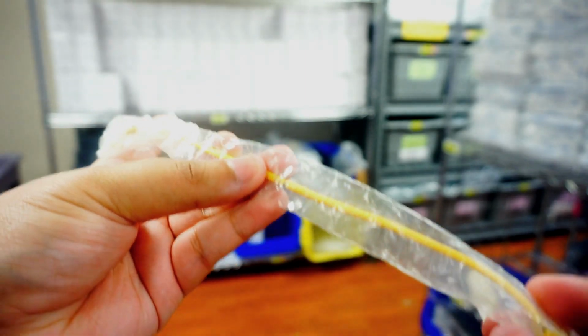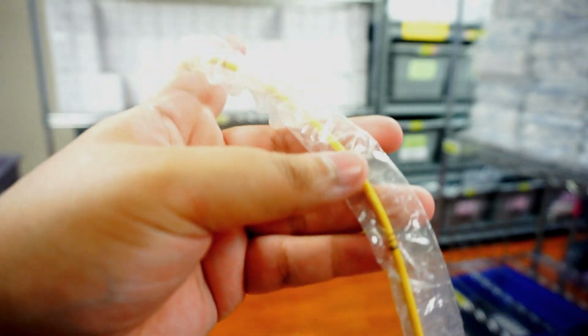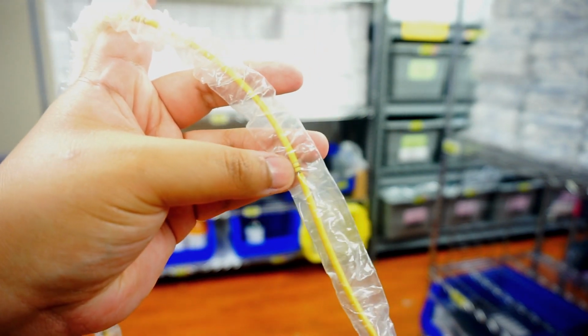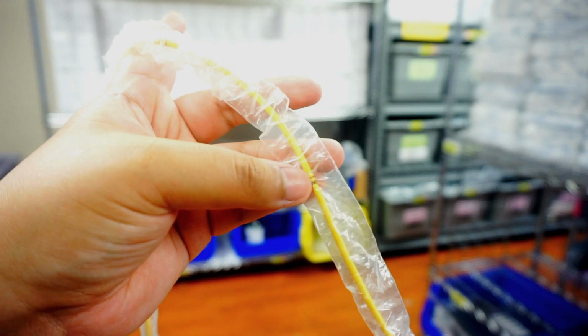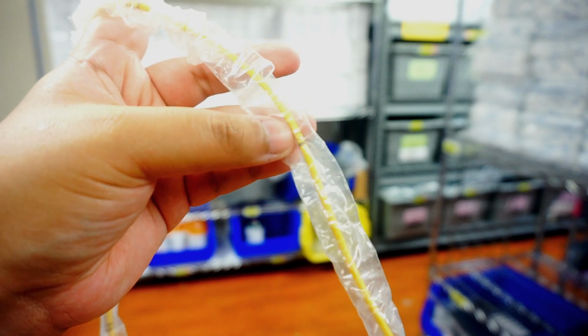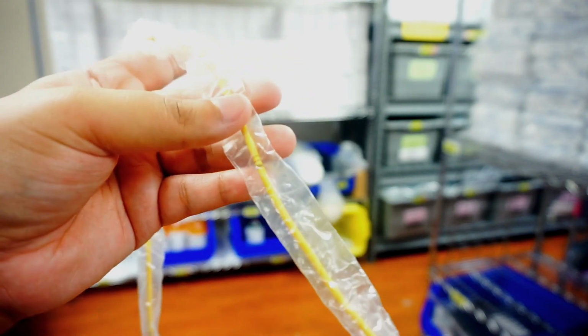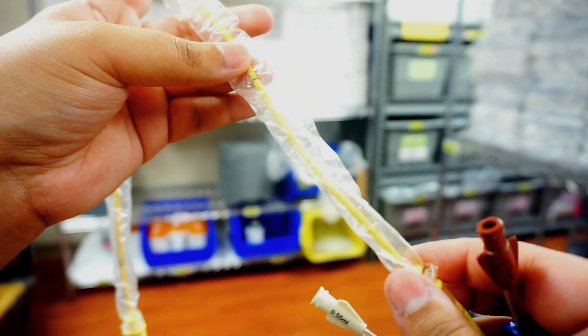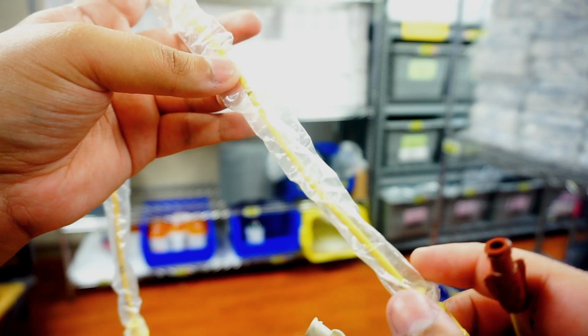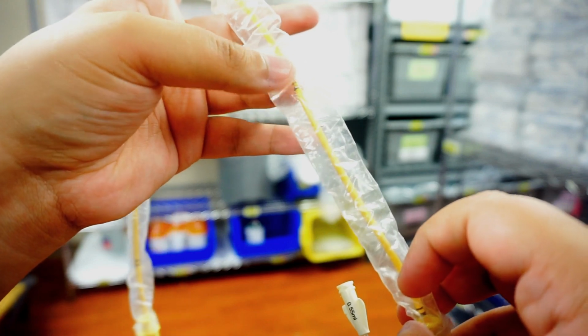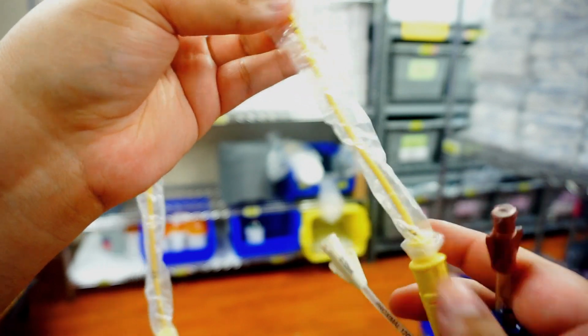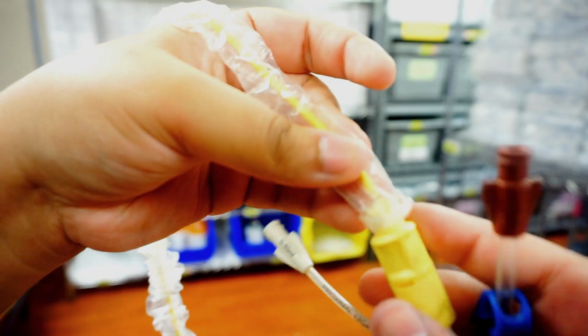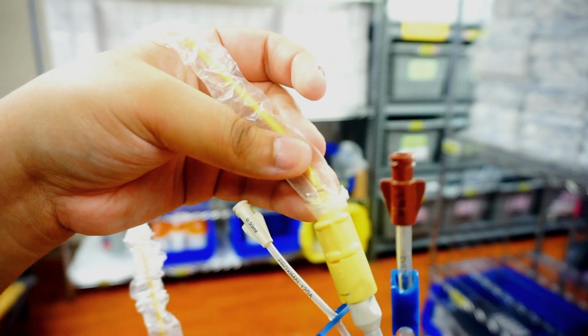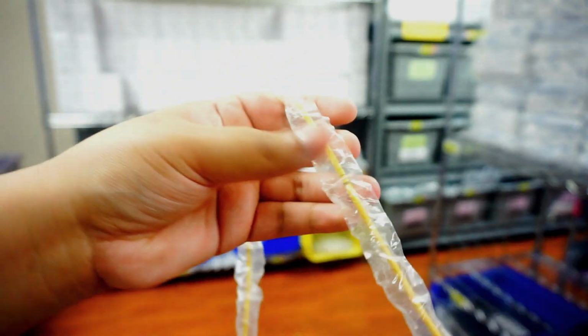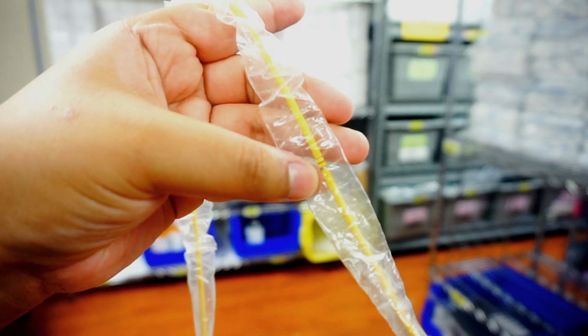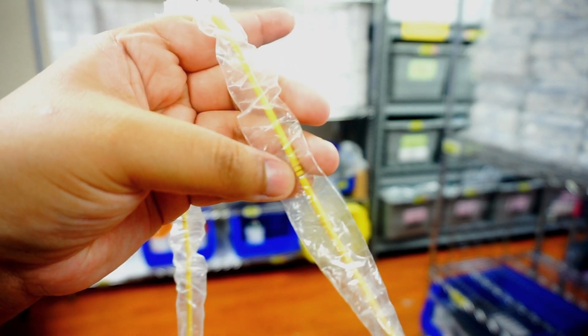Inside your plastic covering, you're going to see your Swan itself. You're going to have marks of measurement on here. So your thicker line is going to be a mark of 50, thin lines are marks of 10. So this mark right here is the 70 centimeter marking. So whenever you're measuring your internal length, what you're going to do is you're going to measure from the yellow hub to the nearest marking you see, and you're going to subtract this measurement from this measurement, and that will be the internal length of the Swan. So here I have it pretty close to the 60. So this one would be in the internal length of the Swan, it would be 60 centimeters. So again, you have your markings. Thick mark is 50 centimeters, thin marks are 10, so this is 70.